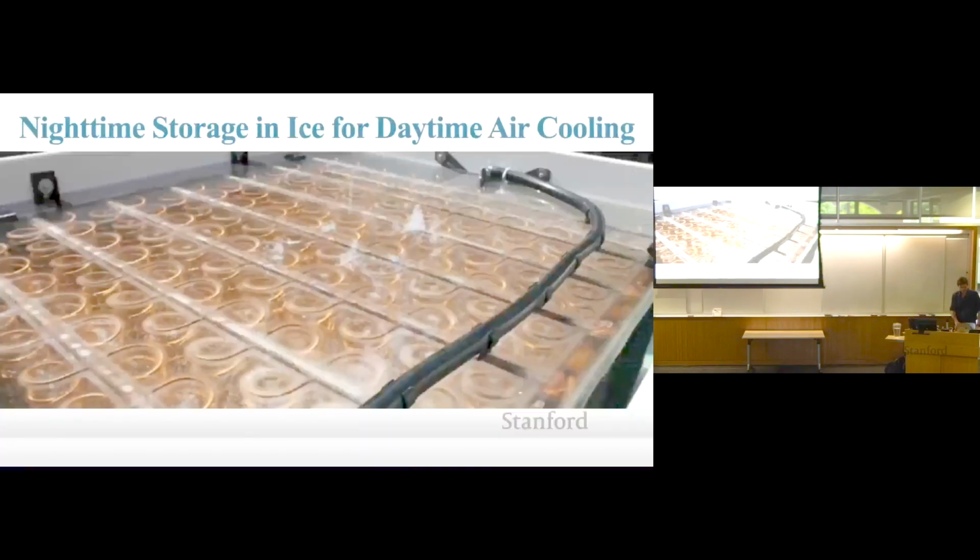All right. Well, here's the ice storage, by the way. This is where I gave you the example. You have these coils in the ice that you send the water through to cool, and then you send cold water to the buildings. But this was around $30 a kilowatt hour of storage, of actual storage capacity. So I think when you asked whether it's levelized cost, I don't know about the borehole. When I say $30 a kilowatt hour, that's the capital cost per kilowatt hour of storage. I think the $1 per kilowatt hour is probably also the capital cost. But I know for batteries, the capital cost is like $100 to $150 a kilowatt hour of capacity.